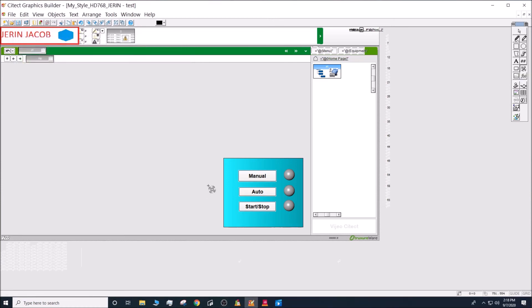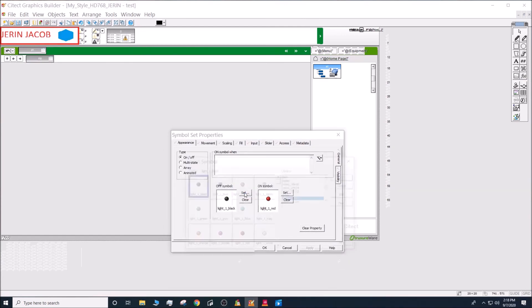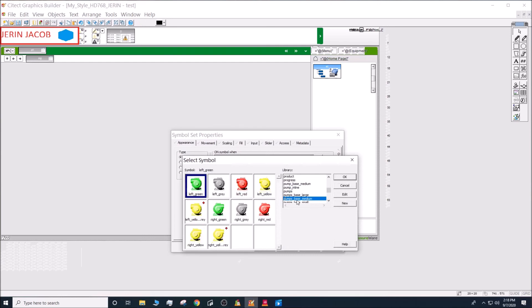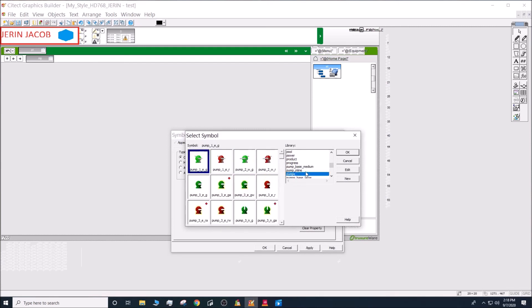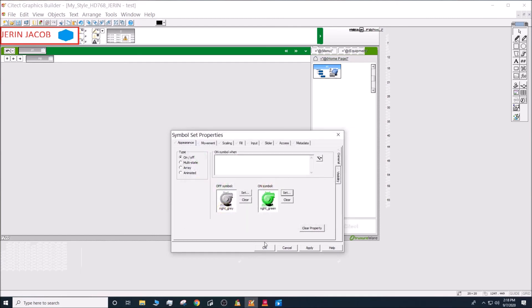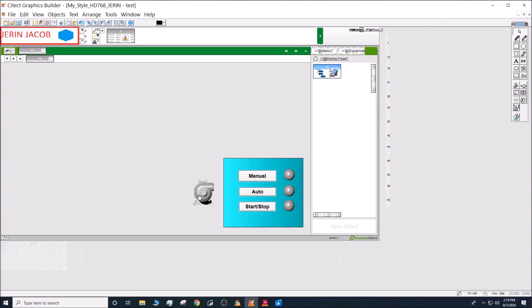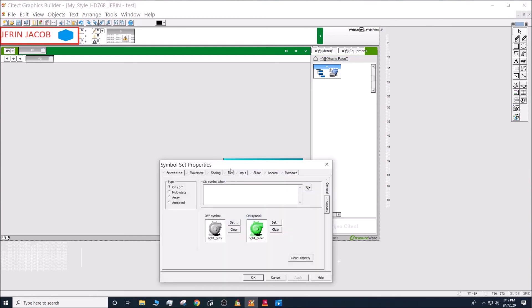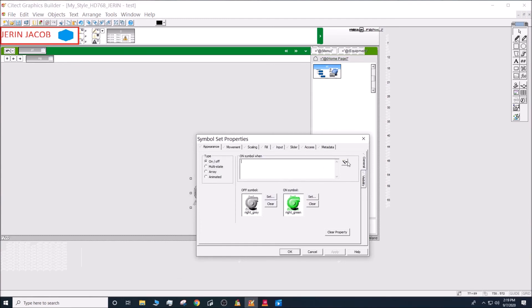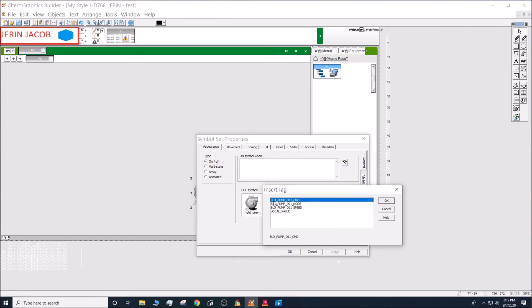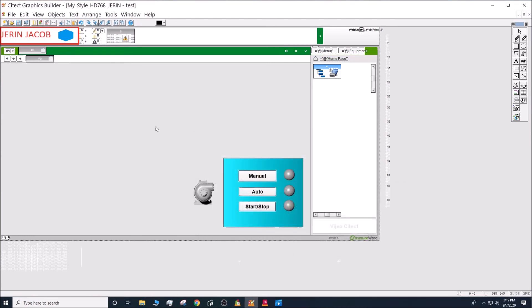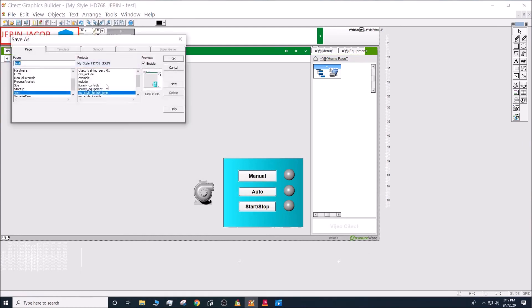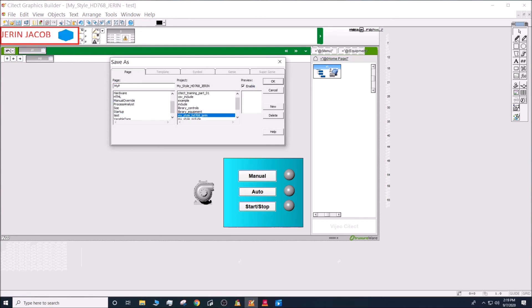Next, let's add a pump graphic using a symbol set. Search for 'pump base large'. For the off symbol, set the color to gray; for the on symbol, set it to green. The pump symbol should turn green when the tag 'building_pump_command' is true.